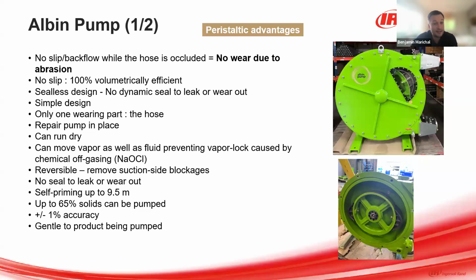This is a sealless design, so there is no dynamic seal to leak or wear out. This is a simple design, especially with this plug-in shaft design between the gearbox shaft and the rotor. Only one wearing part, the hose. We can make the maintenance in place. We can run dry this technology.